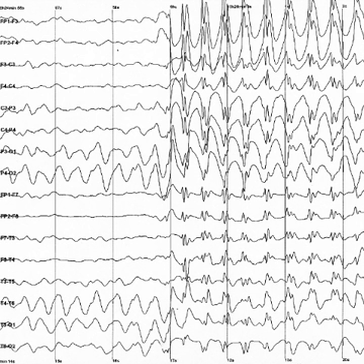ECG artifacts are quite common and can be mistaken for spike activity. Because of this, modern EEG acquisition commonly includes a one-channel ECG from the extremities. This also allows the EEG to identify cardiac arrhythmias that are an important differential diagnosis to syncope or other episodic attack disorders. Glossokinetic artifacts are caused by the potential difference between the base and the tip of the tongue. Minor tongue movements can contaminate the EEG, especially in Parkinsonian and tremor disorders.